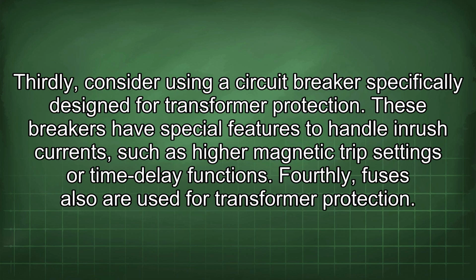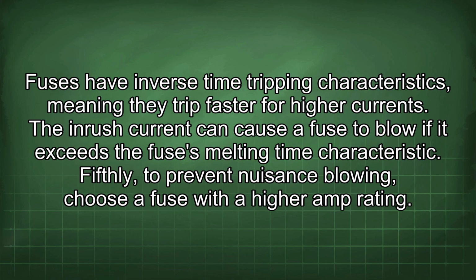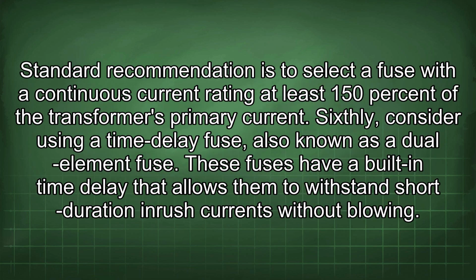Thirdly, consider using a circuit breaker specifically designed for transformer protection. These breakers have special features to handle inrush currents, such as high magnetic trip settings or time delay functions. Fourthly, fuses also are used for transformer protection. Fuses have inverse time tripping characteristics, meaning they trip faster for high currents. The inrush current can cause a fuse to blow if it exceeds the fuse's melting time characteristic. Fifthly, to prevent nuisance blowing, choose a fuse with a higher amp rating. Standard recommendation is to select a fuse with a continuous current rating at least 150% of the transformer's primary current. Sixthly, consider using a time delay fuse, also known as a dual element fuse. These fuses have a built-in time delay that allows them to withstand short duration inrush currents without blowing.